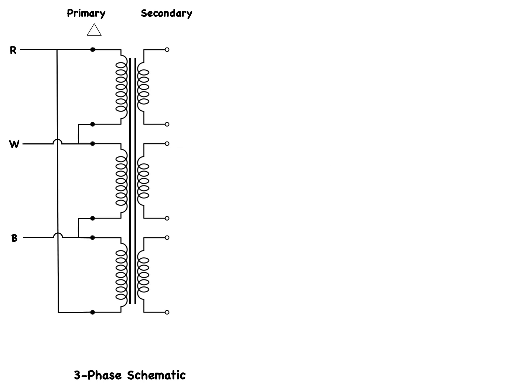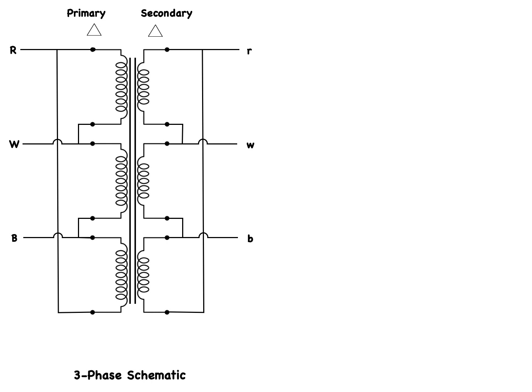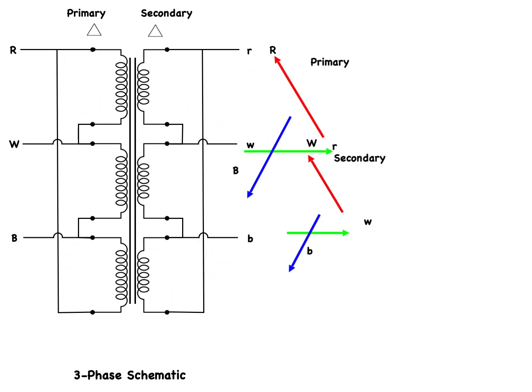Let's return to the delta-connected primary and connect the secondary in delta as well. The top of each winding is brought out to be the red, white, and blue terminal of the secondary side. Remember that the primary side is connected to the phase-to-phase voltages of the system. Since the primary winding is magnetically linked to the secondary winding, the secondary voltage in that winding will be in phase with the primary winding voltage. The same is true for each of the transformer windings. When we plot the vectors of the primary and secondary sides, they look like this.